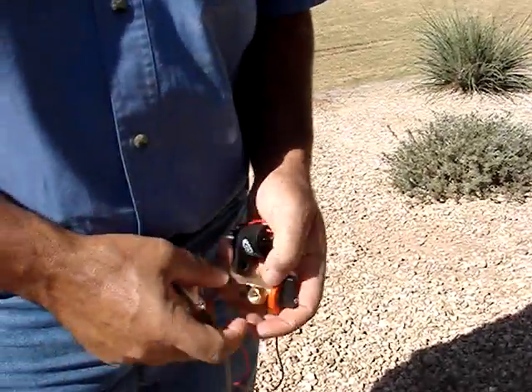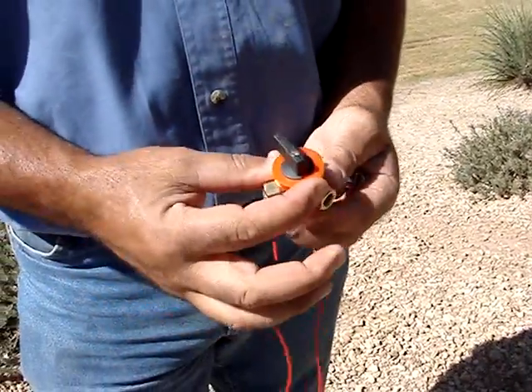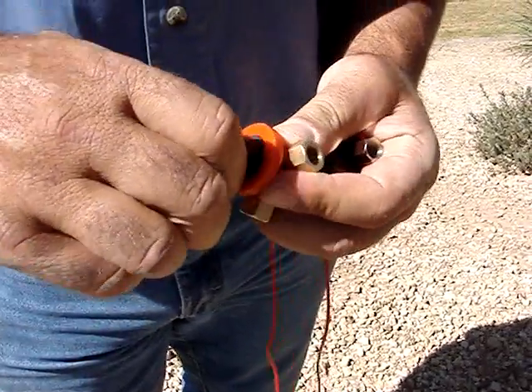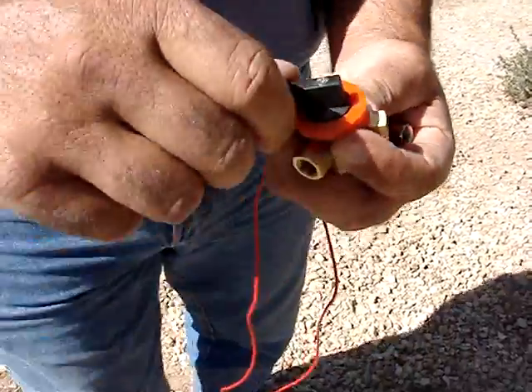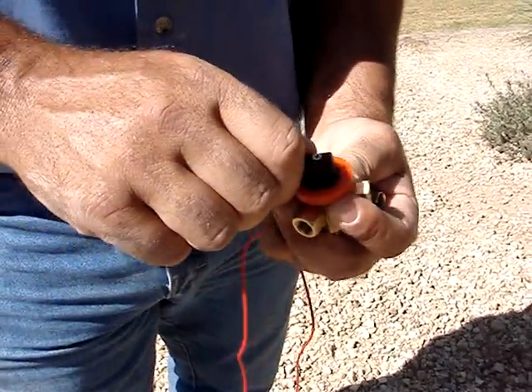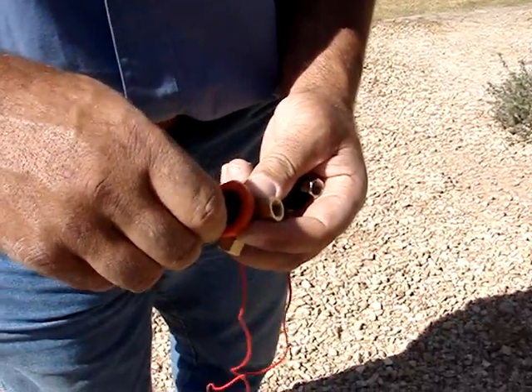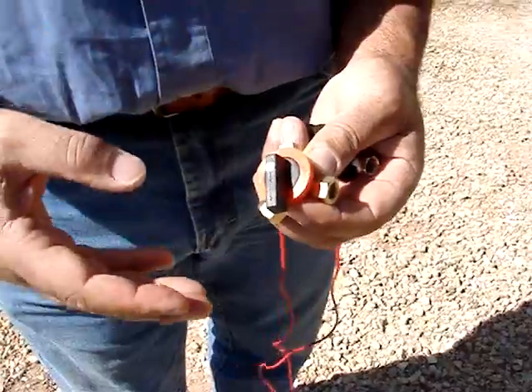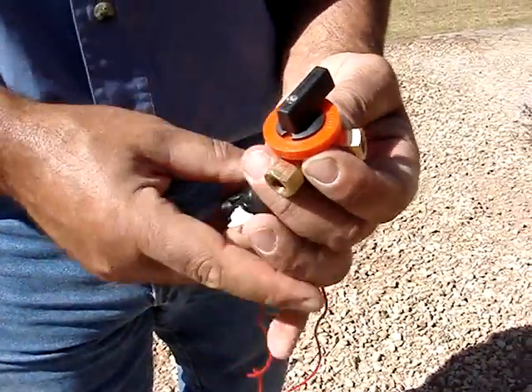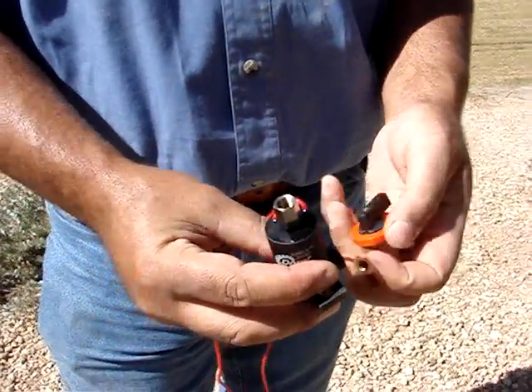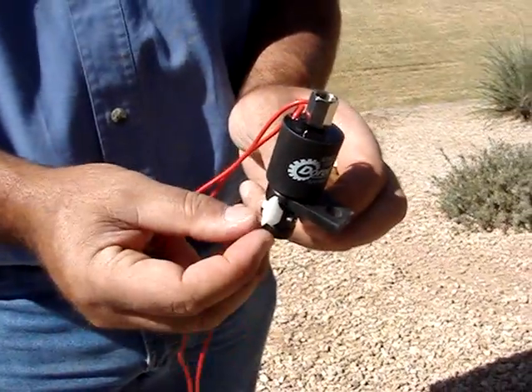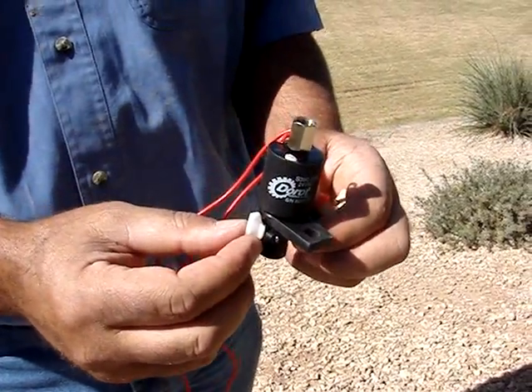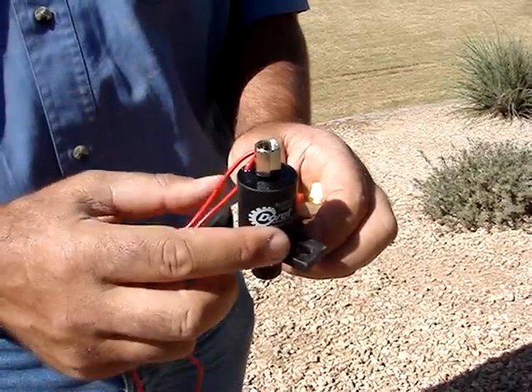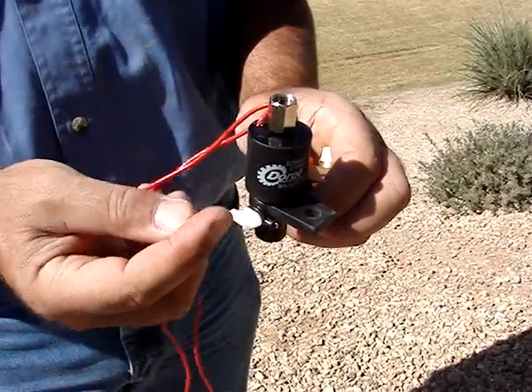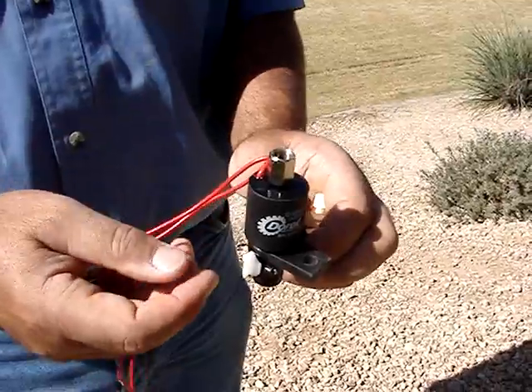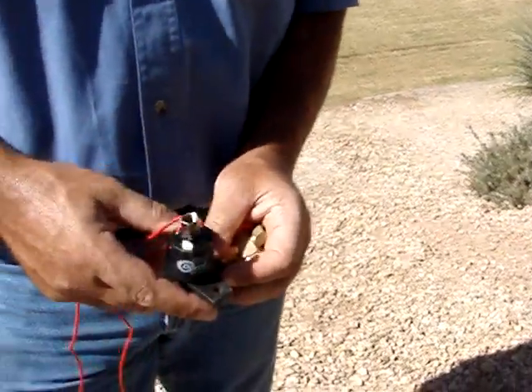Now I'm going to talk a little bit about the valve itself. The 3-way selector is a very nice tool for doing diagnostic work. If we want to establish whether the valve opens or closes, we can turn it to the closed position and the valve should close. We turn it to the open position, the valve opens. Now we've established that the valve is functioning properly. So now we turn it to the auto position. Now the solenoid has control of the valve. The solenoid also has a bypass on it. When it's in this position, straight up with the solenoid, when it gets energized, the valve functions. We can bypass that by turning a little lever. It just pushes the plunger up. So it gives us more ability to do diagnostics.